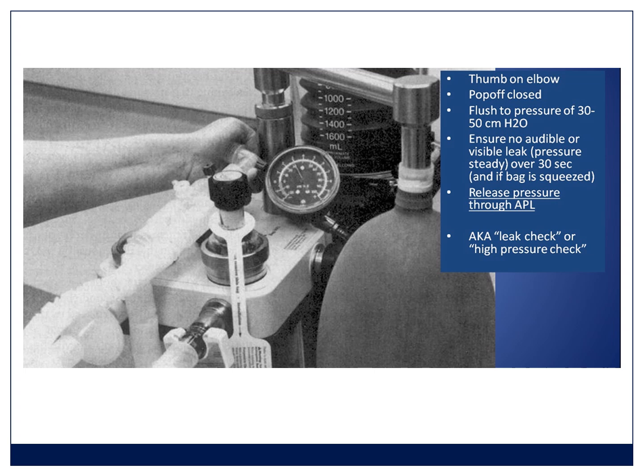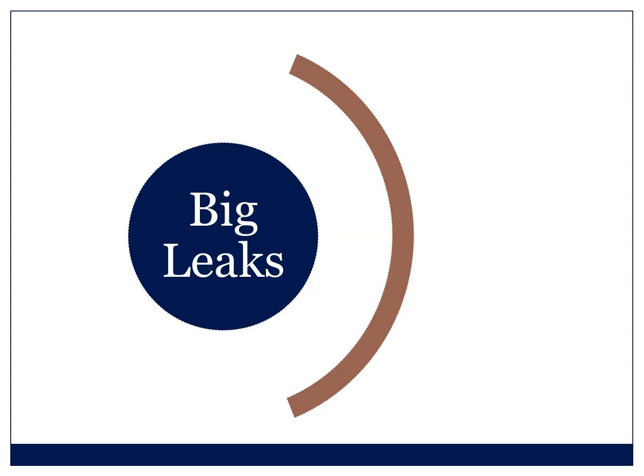Some people use the high pressure test, which is what I've explained. You can occlude the Y-piece with your thumb, and you flush the pressure up, and then you see how much gas is required to keep that pressure up. And if you are losing gas, you can actually put your ear all around the circuit and around the bag and try and listen for where the leak is coming from.